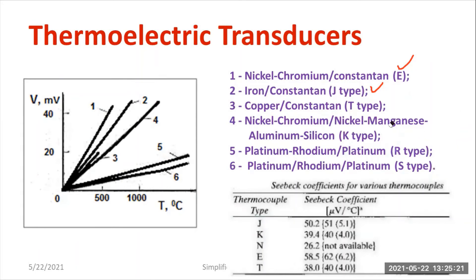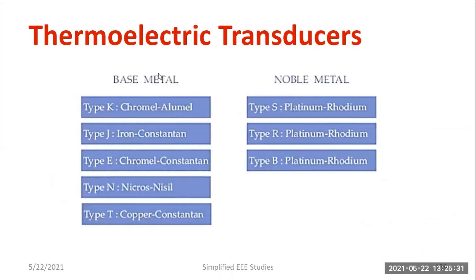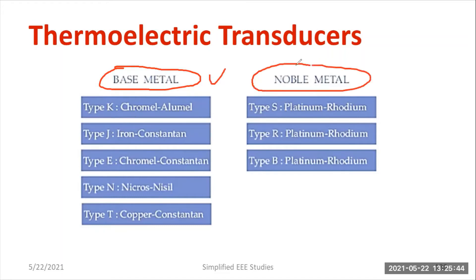The Seebeck coefficient varies with respect to the particular combination like J-type, T-type, etc. There are two categories of thermocouple combinations: base metal — which includes K, J, E, N, and T types — and noble metal, which includes platinum-rhodium type S and platinum-rhodium type R. For example, Nicrosil-Nisil is one of the base metal combinations.